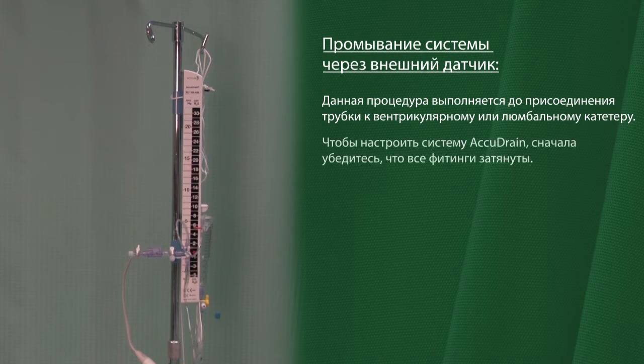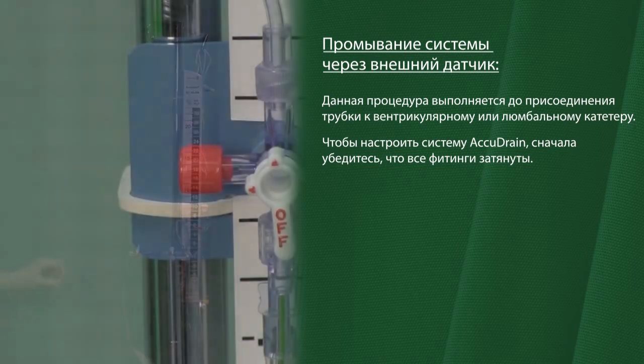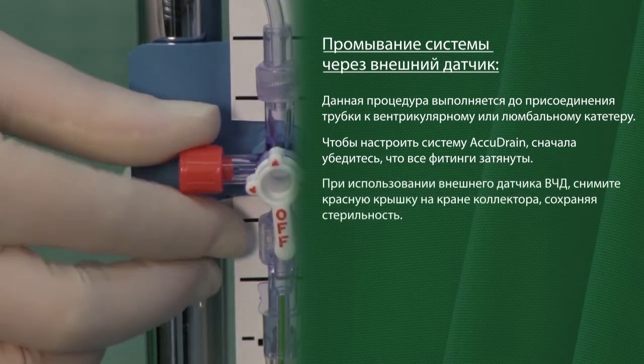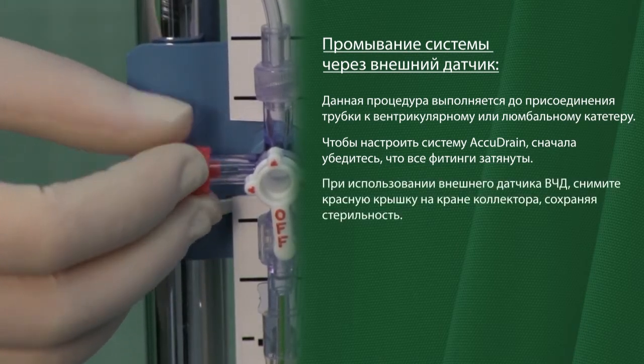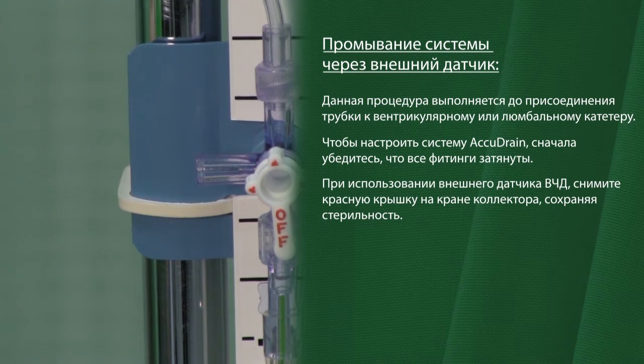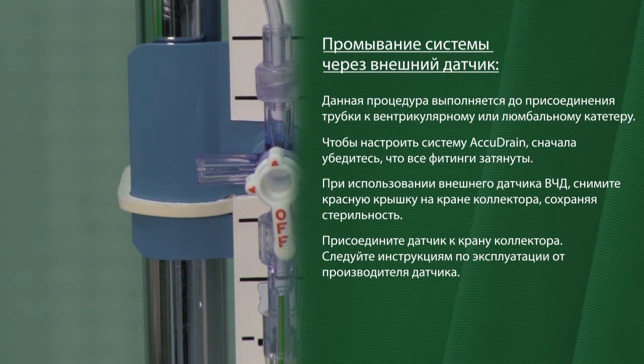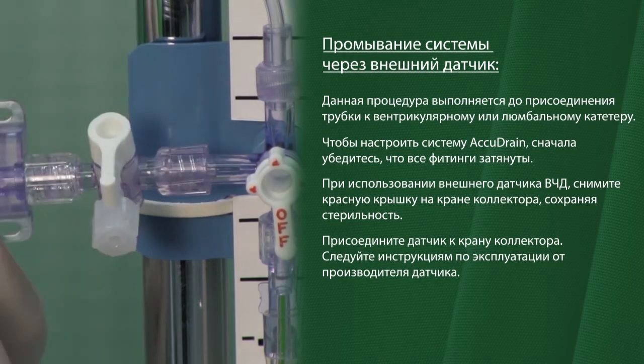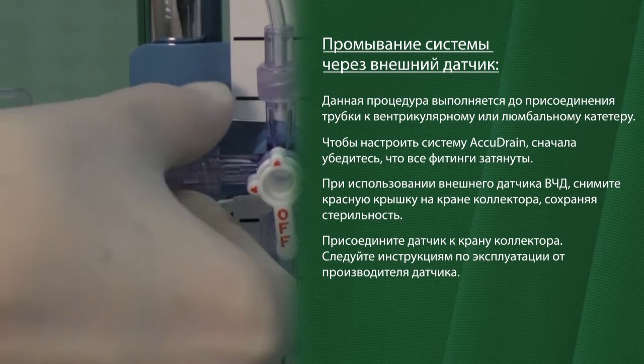To set up the ACCUDRAIN system, first check that all fittings are tightened. When using an ICP external transducer, remove the red cap on the manifold stopcock, maintaining sterility. Attach the transducer to the manifold stopcock. Follow instructions for use from the transducer manufacturer.